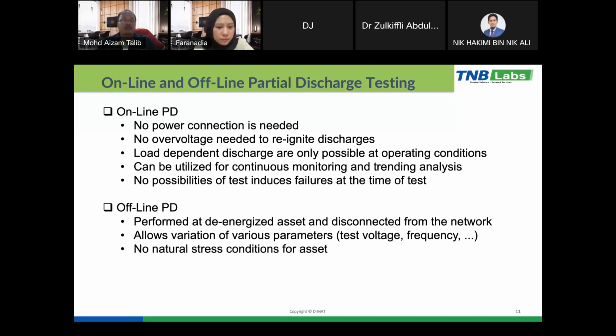Then in terms of online and offline partial discharge testing, we can test the partial discharge through online or offline. Online means that we carry out the measurements without interruption of the power supply. It means that we do not need to shut down the electrical equipment. For example, we don't need to switch off the transformer or cable. Through the live operation of the equipment, we can do the partial discharge testing. And then no over voltage is needed. We don't need any high voltage source to trigger the discharge. It depends on the normal operating voltage of the equipment.